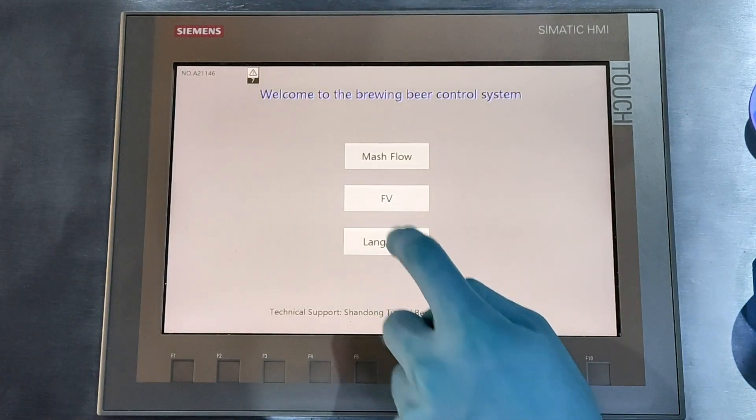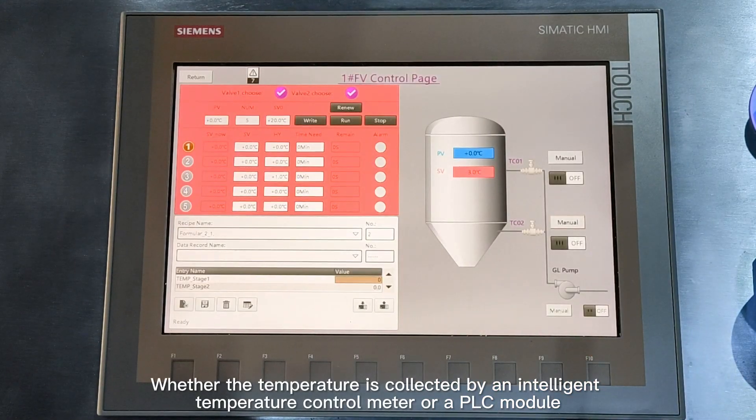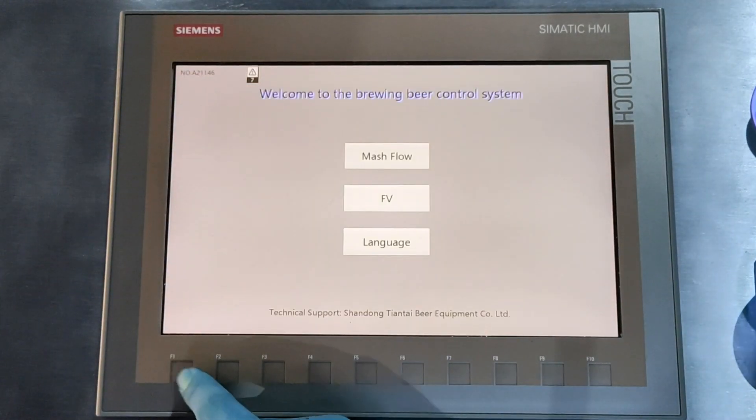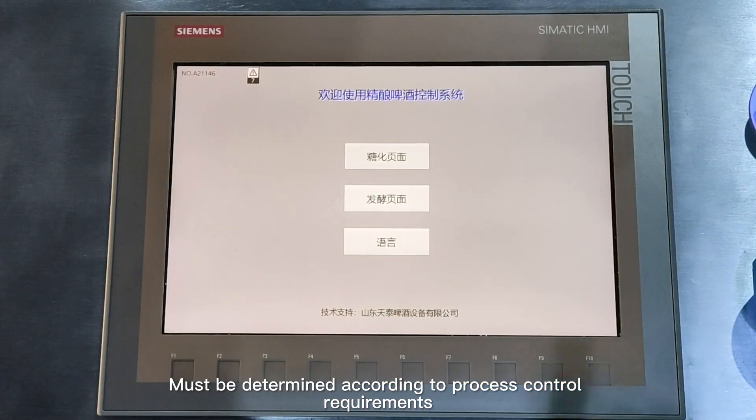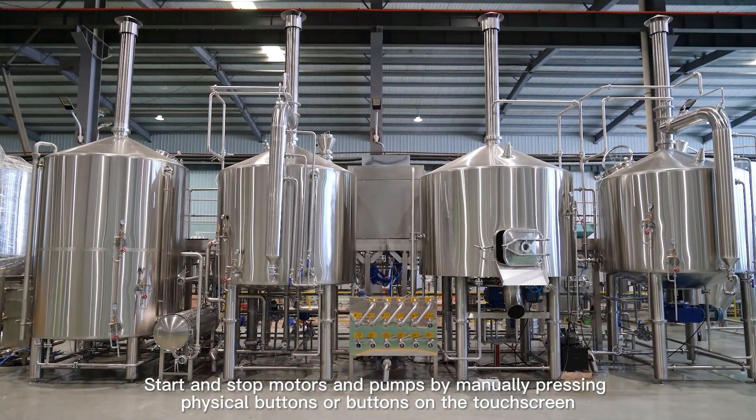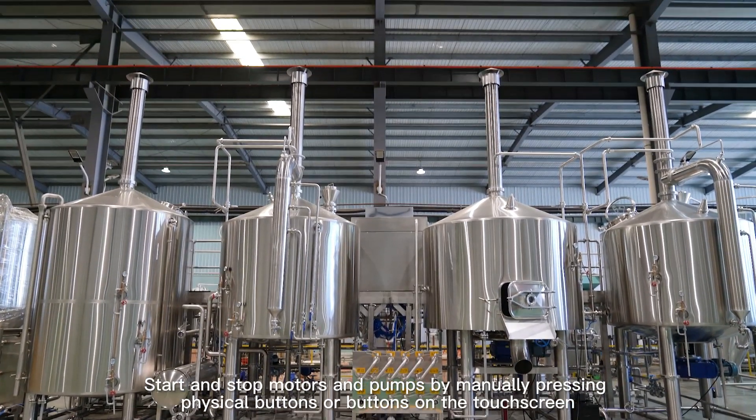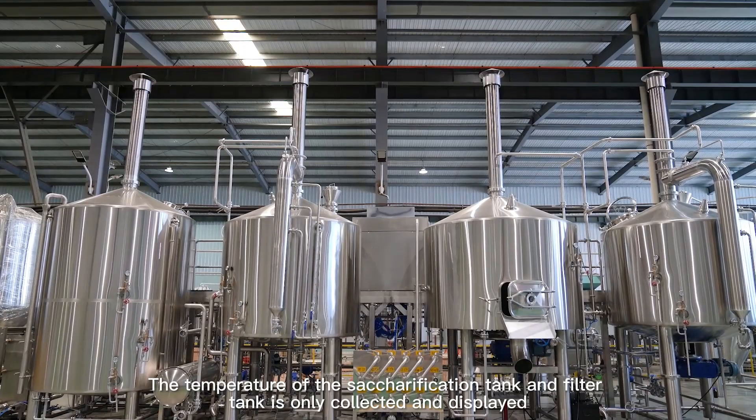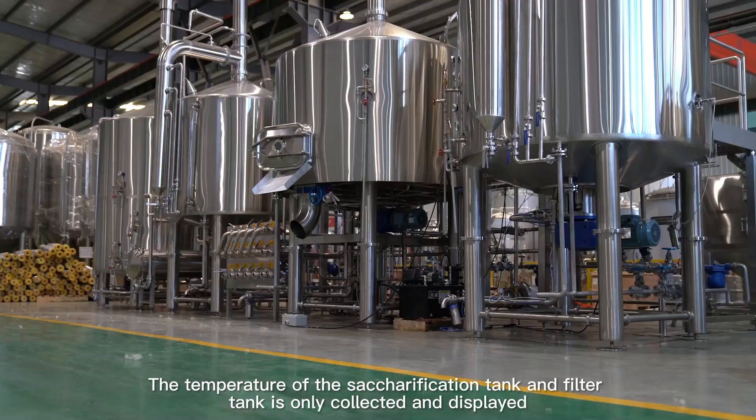Semi-automatic control: Whether temperature is collected by an intelligent temperature control meter or a PLC module must be determined according to process control requirements. Start and stop motors and pumps by manually pressing physical buttons or buttons on the touch screen. The temperature of the saccharification tank and filter tank is only collected and displayed without any processing.